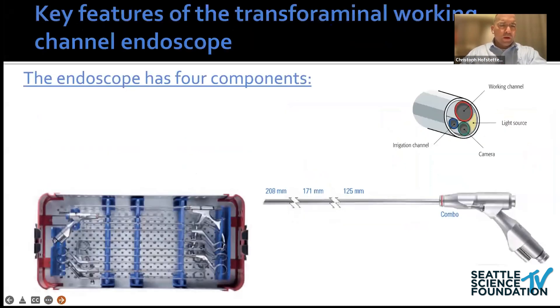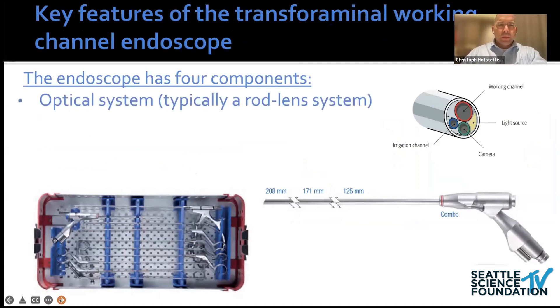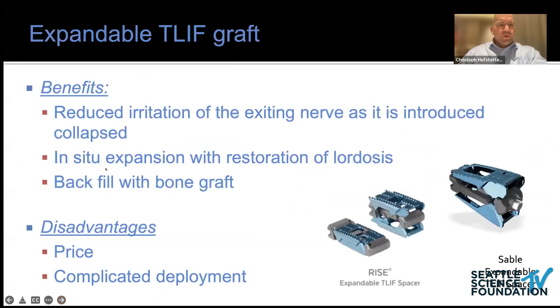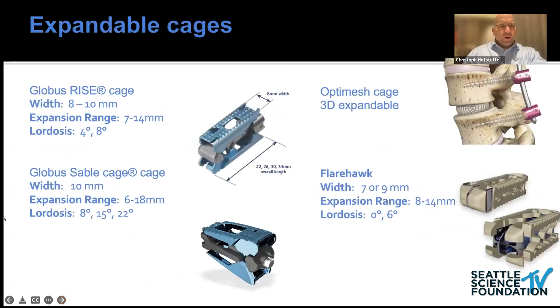Here's a quick overview of an endoscope: four components — optical system, illumination, irrigation channel, and a working channel. Now the rise of expandable T-LIF cages is interesting — it reduces irritation of the exiting nerve root, allows in-situ expansion and restoration of lordosis, and you can backfill bone graft. The disadvantage is price, though there's movement to bring that down, and deployment is complicated. On the market we have two-dimensionally expandable cages from Globus, the Optimesh cage, and the Flare Hawk — a three-dimensional option. The additive technology products on the right are interesting: you put a shell in and add more material, versus the left-side products which expand from one delivered package.